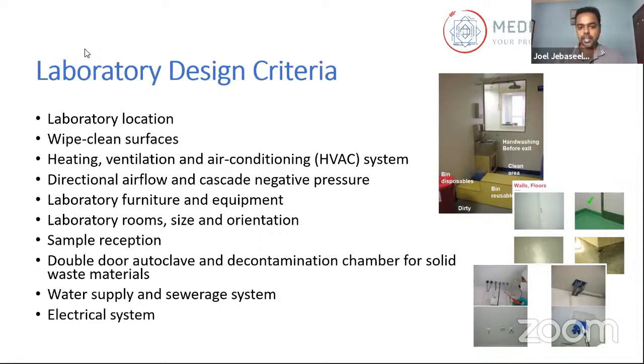Directional airflow and cascade negative pressure - this is again where the HVAC system works. All these labs are always under negative pressure. When I say cascading, I mean the corridor will have slightly higher pressure than the rooms, so the air moves from the corridor into the room, and your biosafety cabinets will have the highest suction, the highest negative pressure. So the air moves from outside the building into the corridor, into the various rooms, and gets extracted out through the exhaust. That's why the HVAC system is so important.